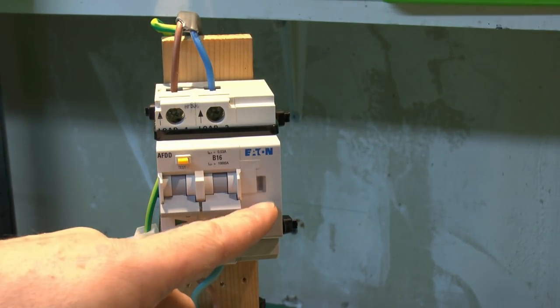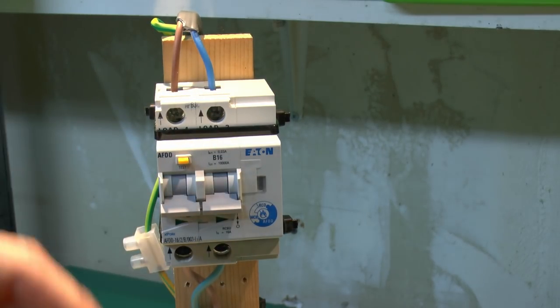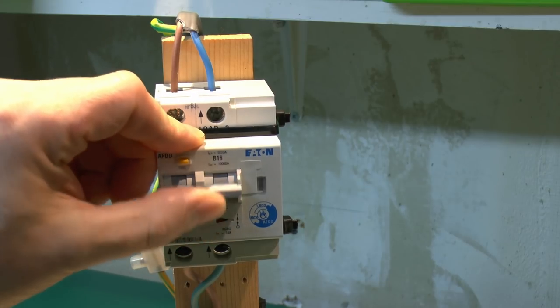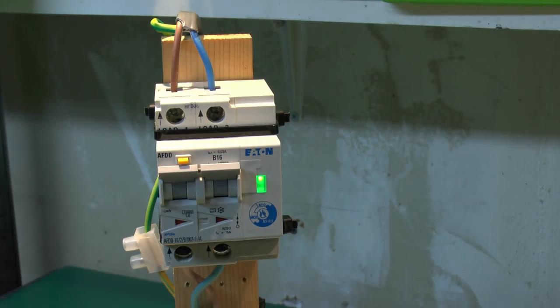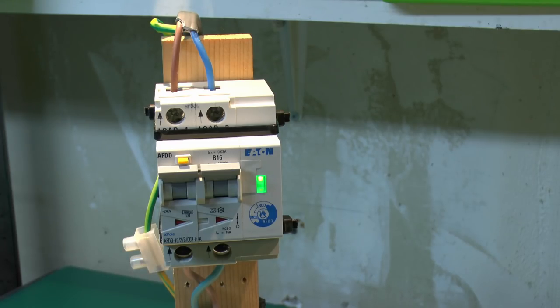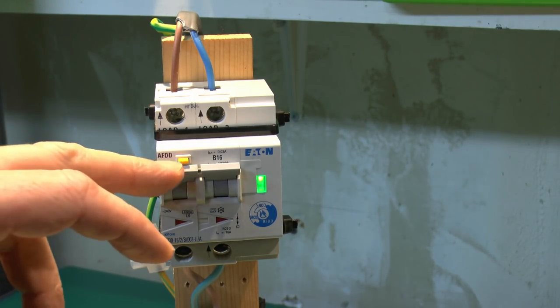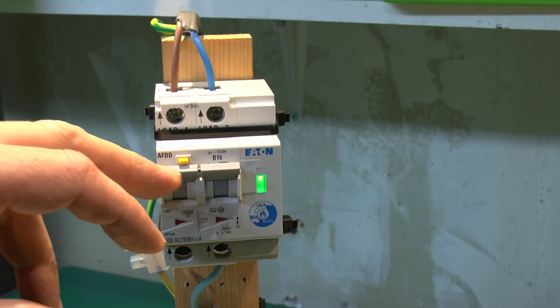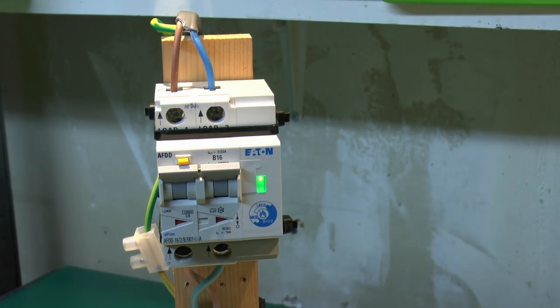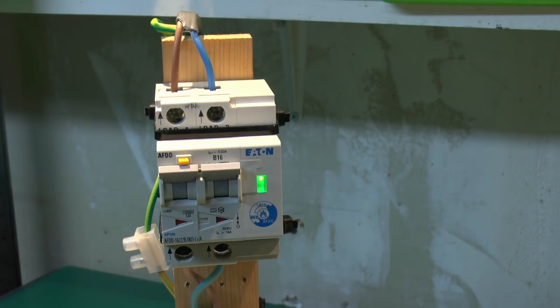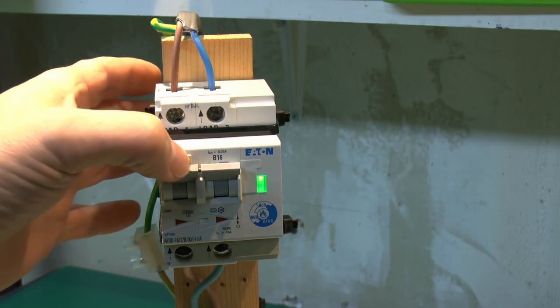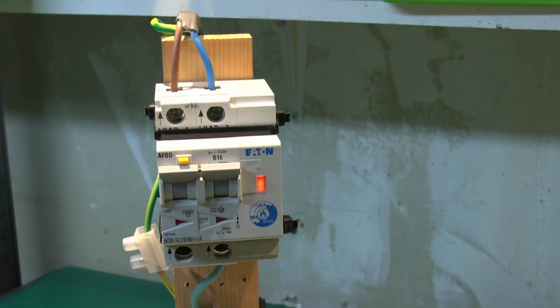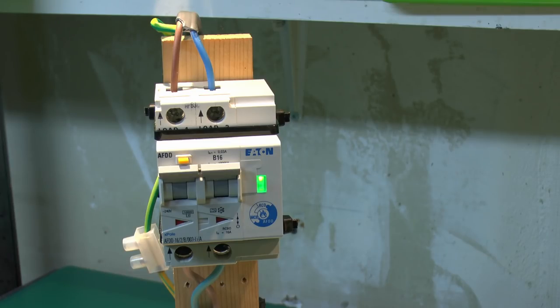So the power is on. So if we turn it on we should see the green indicator here, and according to the instructions it should cycle through the colours there to show that it is actually working correctly. So there we go. So we have the red, amber and green, and there was a bit of a gap. And then it's got the green, which signifies normal operation. So it seems to be working as expected. And we can see the red mechanical indicators in the window, obviously showing that it is on. One thing I don't like about this is the test button, which is here, is incredibly close to the position of the actual switch there. There's a tiny little gap between it, but literally it's right on the actual actuator lever there, which is not particularly wonderful. But anyway, that is now on. If we press the test button, then it does trip. And again it just goes through the same cycle as before. So no real surprises there.